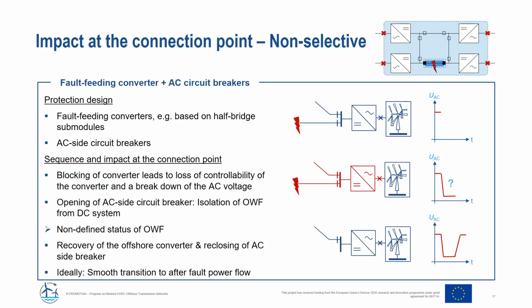So during the fault clearing process, the converters block for self-protection, and this leads to a loss of controllability of the converter and a breakdown of the AC voltage. The fault clearing itself is achieved by opening of the AC side circuit breakers, which takes several 10 milliseconds, in the range of 40 to 60. And then when the AC circuit breaker is opened, this leads to an isolation of the offshore wind farm from the DC system. So we have a non-defined status of the offshore wind farm in this situation. For recovery of the system, the offshore converter has to be recovered and the AC side circuit breakers have to be reclosed. And ideally, we would have a smooth transition to after-fault power flow from the offshore wind farm. So this is a very demanding situation for the offshore wind farm with a non-defined status in between. And this will be discussed in more detail in the following section.